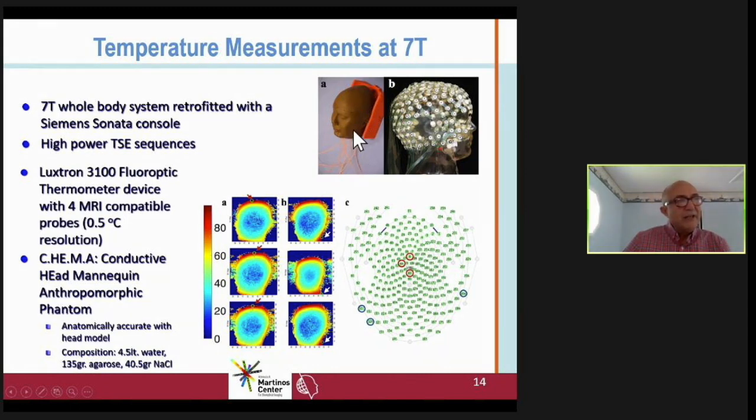We inserted a number of thermal probes, which were in very close contact with the electrodes themselves. Since the probes are connected through plastic fibers, we could only put a certain number of sensors, because otherwise the entire phantom would become plastic.